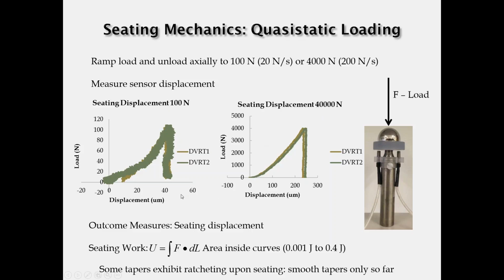What you can see in these plots is that the head sits down onto the taper. In the case of 4,000 newtons, that's roughly a 250 micron seating displacement, and with 100 newtons you only get maybe 40 microns of seating displacement. So these curves represent the nature of the engagement mechanism between the tapers.